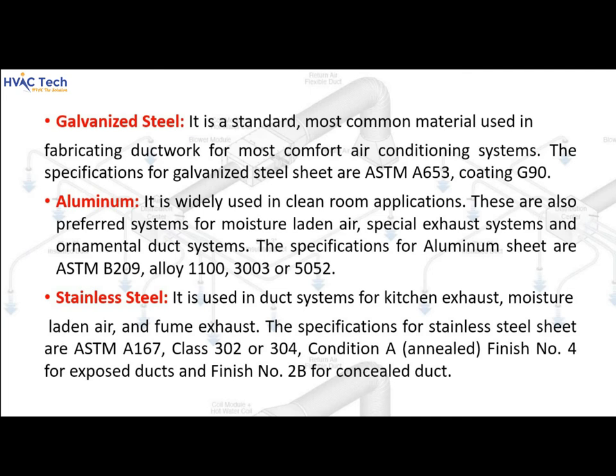Galvanized steel is the standard and most common material used in fabricating ductwork for most comfort air conditioning systems. The specifications for galvanized steel sheet are ASTM A653, coating G90.